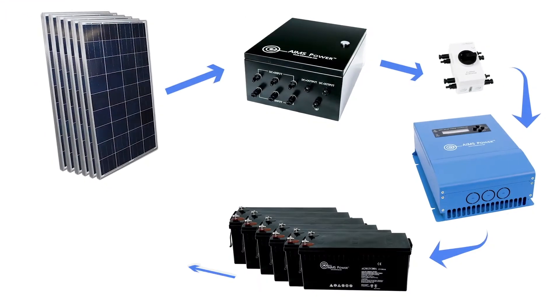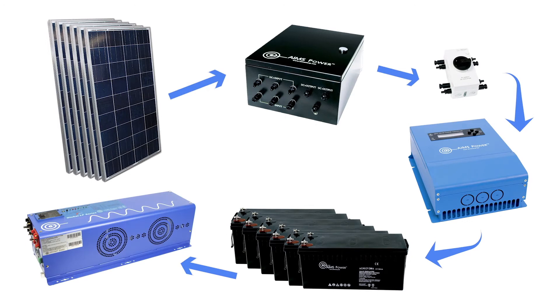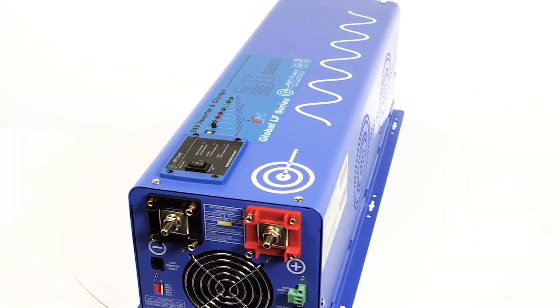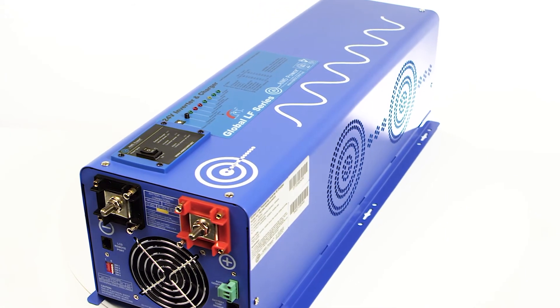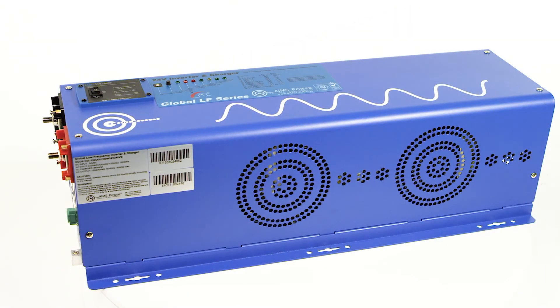The battery bank provides power to the inverter charger. We include the AIMS Power 6000-watt Pure Sine Inverter Charger that outputs split phase 120 and 240 volts AC. This unit has a 24-volt DC input and a 240-volt AC input for charging and bypass. The inverter has a powerful 18,000-watt surge for 20 seconds and is built with a low-frequency platform.